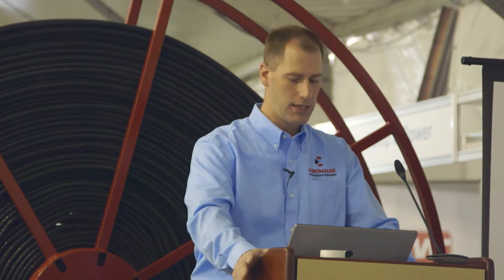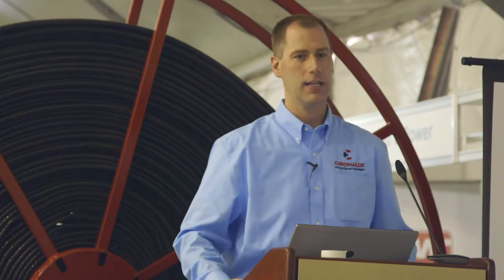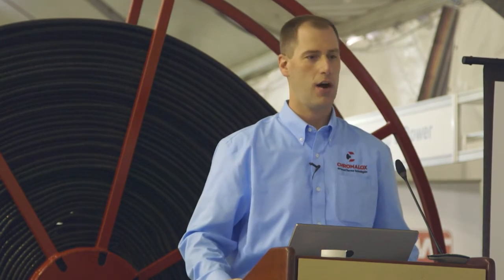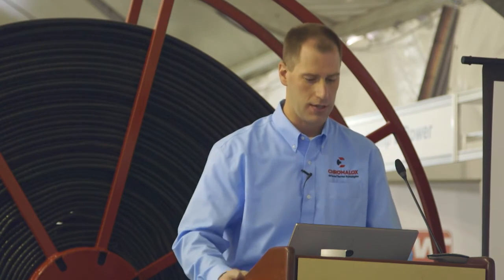You can apply that exact same application at medium voltage, and suddenly you reduce down to just a few hundred amps and minimal circuits, eliminating the transformer. The installation cost reduction is tremendous, and we're talking about just a 2.5 megawatt load. These systems are obviously capable of much, much larger loads than that.